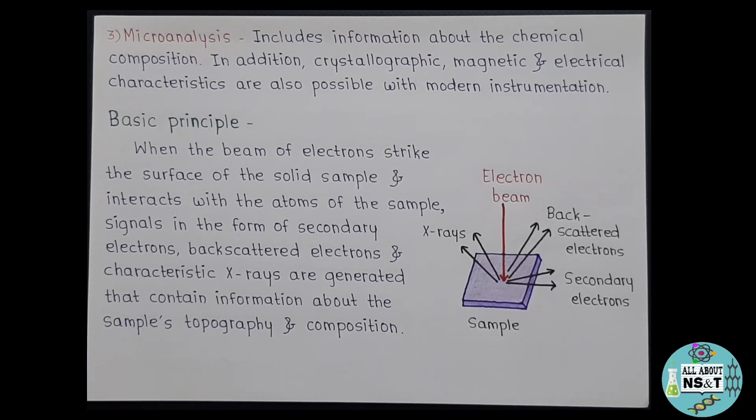Okay then, now let's get into knowing about working principle and instrumentation of SEM. Firstly, let's understand its basic principle. So when the beam of electrons strike the surface of the solid sample and interacts with the atoms of the sample, signals in the form of secondary electrons, backscattered electrons, and characteristic x-rays are generated that contain information about the sample's topography and composition. So as you can see in this picture, when the electron beam hits the sample surface, there is interaction between them which leads to the generation of secondary electrons, backscattered electrons, and x-rays.